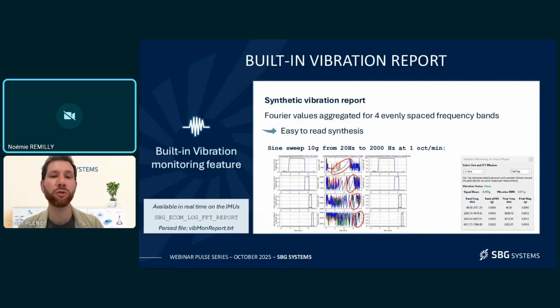So we've decided to also, as part of the same vibration monitoring feature, put something easier to read, easier to understand, which is the synthetic vibration report, where on top of providing the full spectrum that you saw before, we provide the Fourier value aggregated for 4 evenly spaced frequency bands, and for each frequency band, we provide the GRMS, the peak frequency, and the magnitude of the peak frequency.